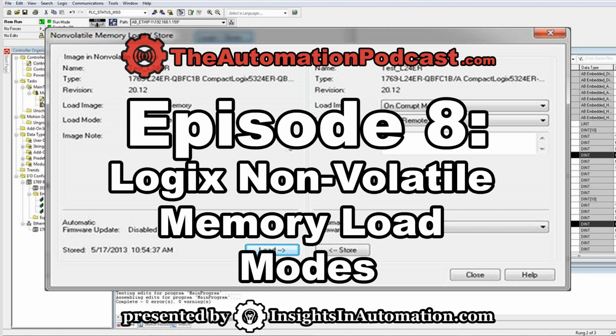This is where we store our program to non-volatile memory, as well as where we would load it from non-volatile memory. So for our first test, we're going to store our current program, Program 1, to non-volatile memory with the load image setting set to user initiated. So go ahead, make that change, and then press Store. Now, as RSLogix will tell you, this is going to take a moment, and you're going to have to watch the lights on the front of the processor to see when it's done. But after a minute or 2, your program, in our case Program 1, will be stored to non-volatile, and you'll be able to reconnect to the processor. So go ahead and reconnect to the processor now.